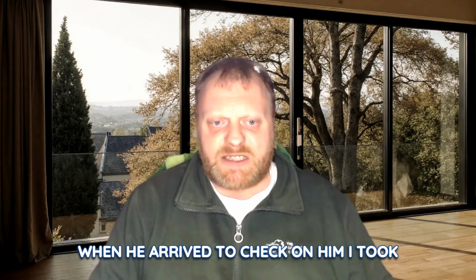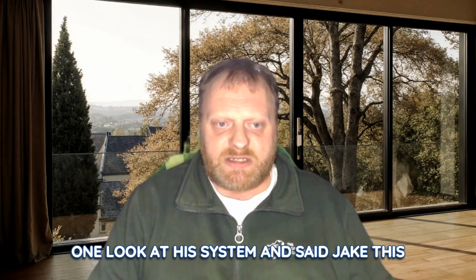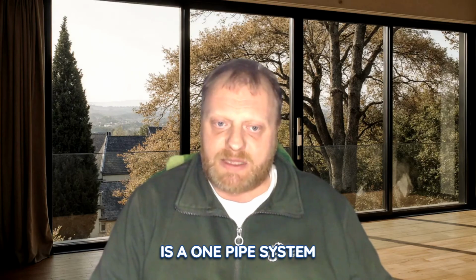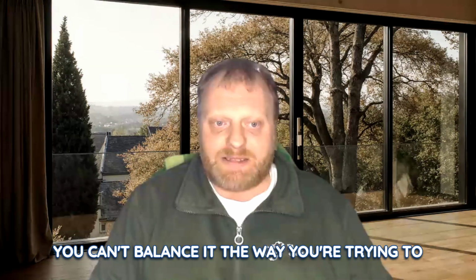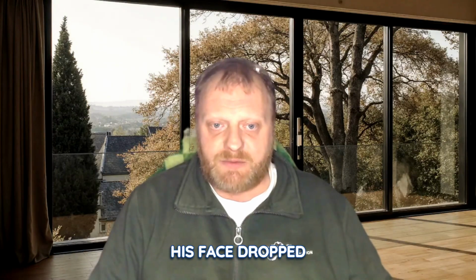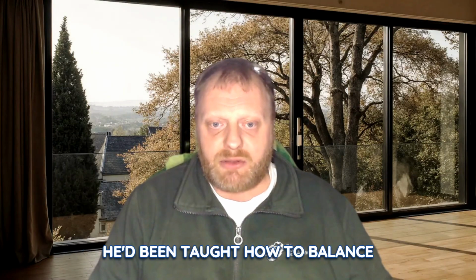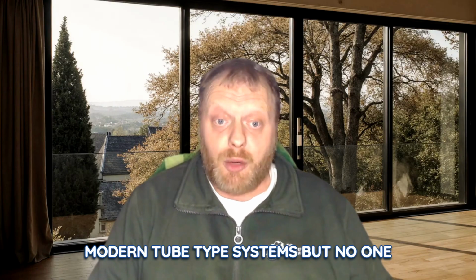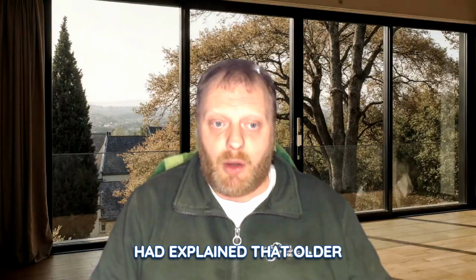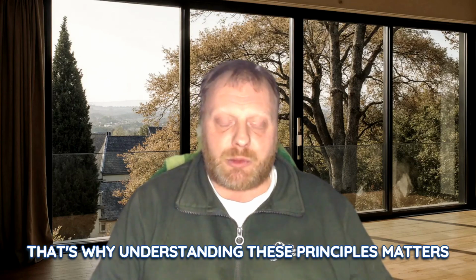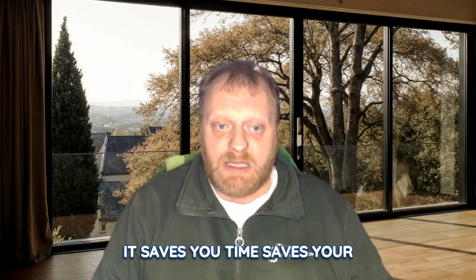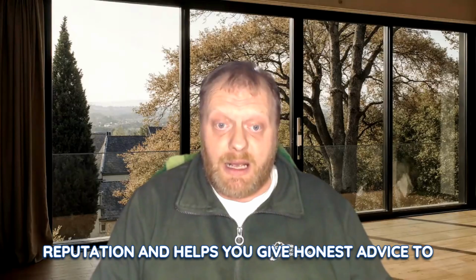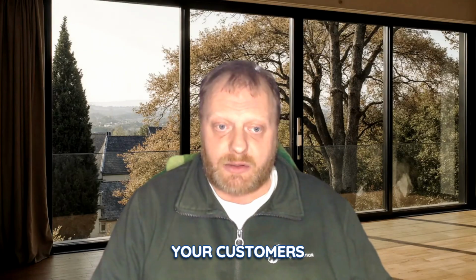When I arrived to check on him, I took one look at the system and said, Jake, this is a one-pipe system. You can't balance it the way you're trying to. His face dropped. He'd been taught how to balance modern 2-pipe systems, but no one had explained that older systems work differently. That's why understanding these principles matters. It saves you time, saves your reputation, and helps you give honest advice to your customers.